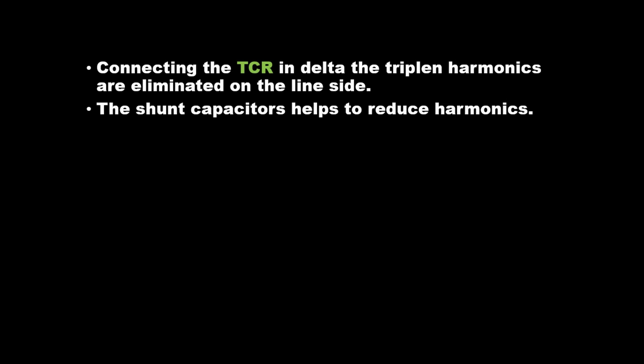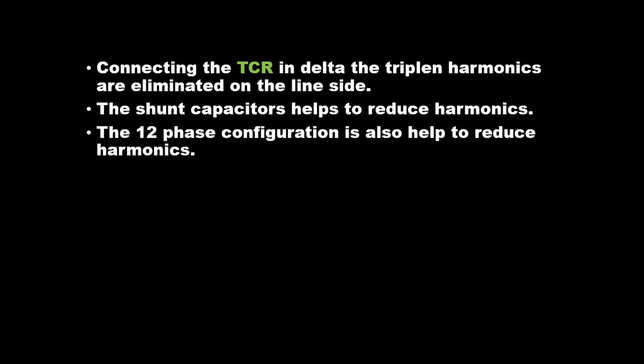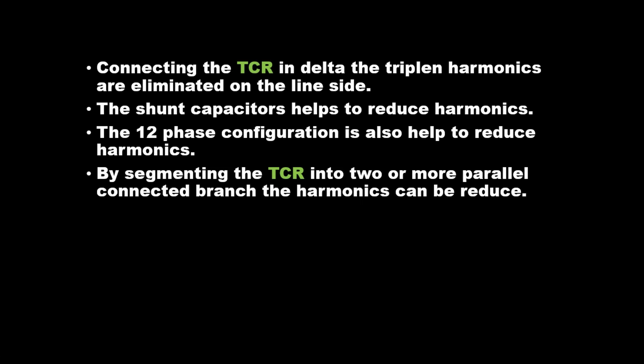Connecting the TCR in delta, the triplen harmonics are eliminated on the line side. The shunt capacitors help to reduce harmonics. The 12-phase configuration also helps to reduce harmonics. By segmenting the TCR into two or more parallel connected branches, the harmonics can be reduced.